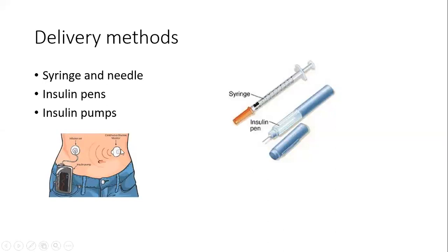Now, a little technology that is coming up, actually picking up in some countries now, is that this continuous glucose monitor will check the blood sugar and send that message to the pump. And that communication, the pump will then decide how much insulin to give, depending on the blood sugar that they are recording here. Blood sugar is going high, the pump will give a little bit more insulin. If the patient is going into hypo, the pump can actually shut and stop giving insulin.